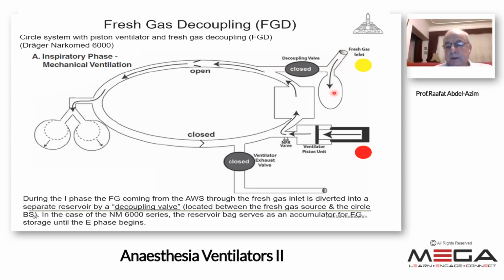bag. I said before, when I described the action of the traditional ascending bellows ventilators, that whenever I start mechanical ventilation, the reservoir bag is isolated and it doesn't move. Observe the reservoir bag during mechanical ventilation using ascending bellows ventilators. You will see it not moving because it is isolated. But in case of using fresh gas decoupling, it expands during inspiration. Why does it expand? Because the fresh gas flow is redirected. It is not going into the inspiratory limb, but it will go into the reservoir bag. So during inspiration, the patient is not given what is coming from the fresh gas flow, but it is stored here in the reservoir bag.